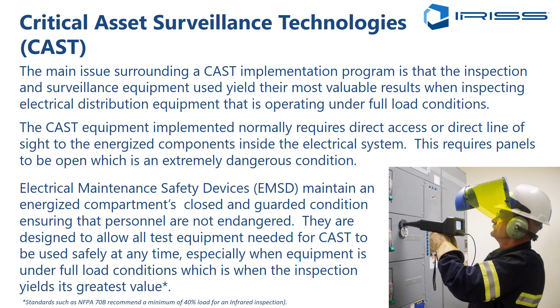So utilising EMSDs, or electrical maintenance safety devices, enables me to use the critical asset surveillance equipment such as infrared and ultrasound, etc., and visual inspection through either windows or ports, because that keeps the panel in an enclosed and guarded condition, which enables me to use the CAST equipment, get the data I need, but never open the panel and never put myself in harm's way.